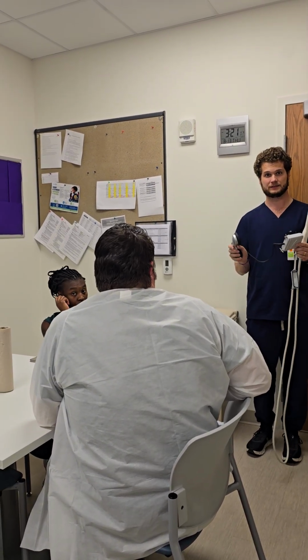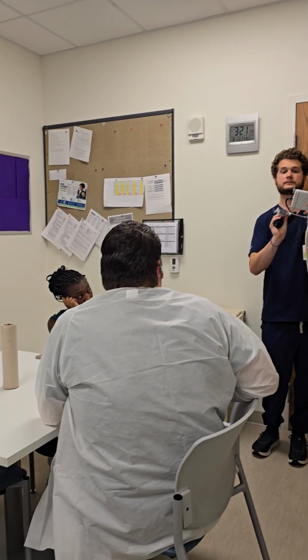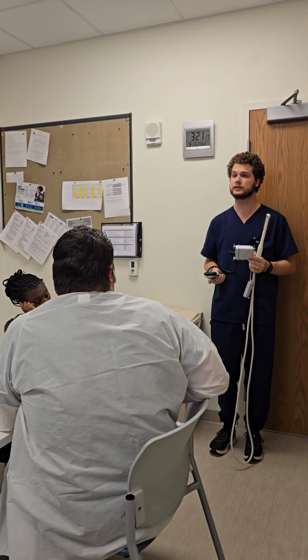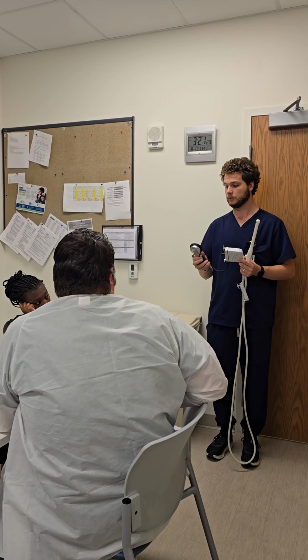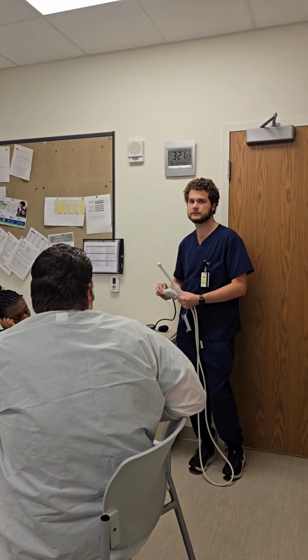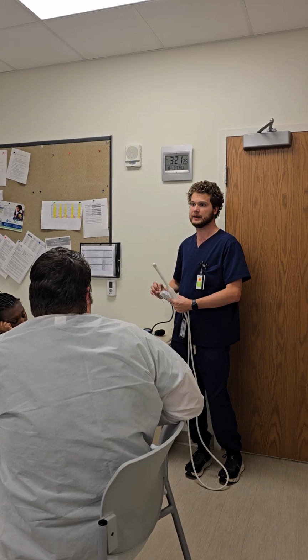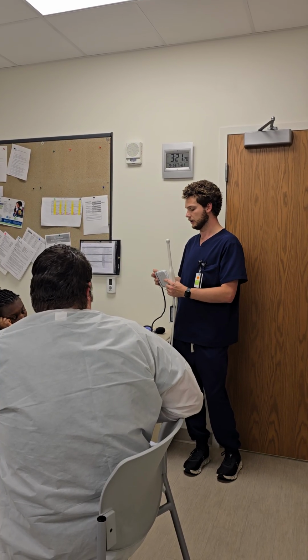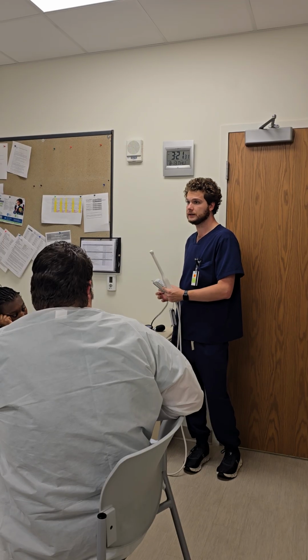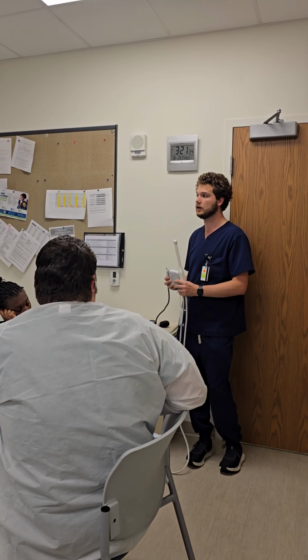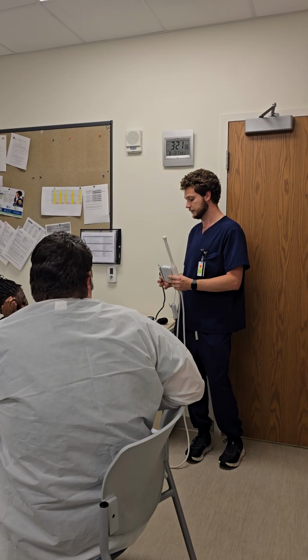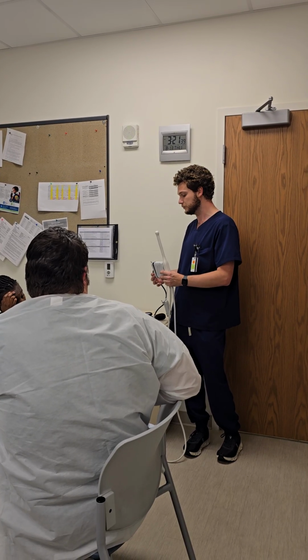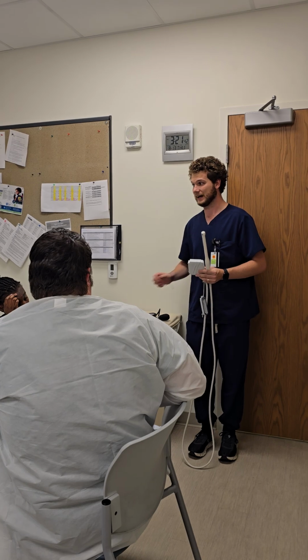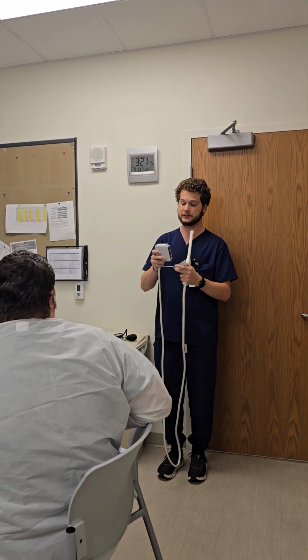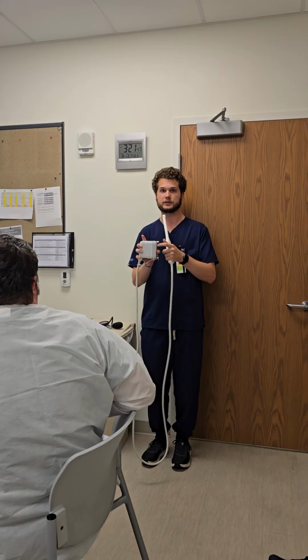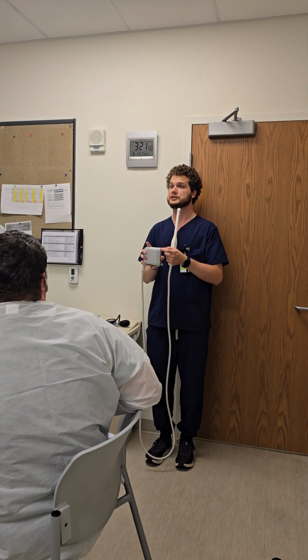Do we take off that other cap? This cap will stay tethered on, just because when we do our next step, when we start reprocessing it, which is going to be hand washing it. Hand washing it, you'll do your normal hand wash, enzymatic detergent, soft bristle brush, clean everything off. Make sure when you're doing this hand wash and you submerge it, you put the cap that's on the tether back on. There's a lot of technology that goes into this, and like I said, if these ultrasound probes break, we can't do the procedure at all. So make sure when you start hand washing it, cap goes all the way on, and you screw the cap all the way tight.